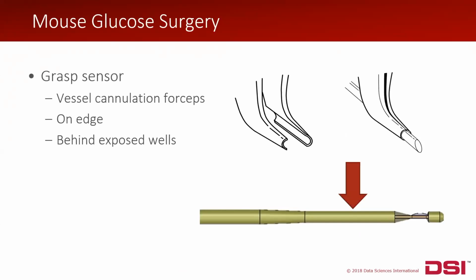We always recommend using a vessel cannulation forceps to hold the sensor to prevent damaging it. The sensor should be held in the channel of the forceps, sitting up on its edge, as you can see here, and not laying down flat. This is going to allow the sensor to bend the correct way as it goes into the aortic arch. The sensor should also always be grasped behind that exposed enzymatic well, grasped near where the arrow is shown here.